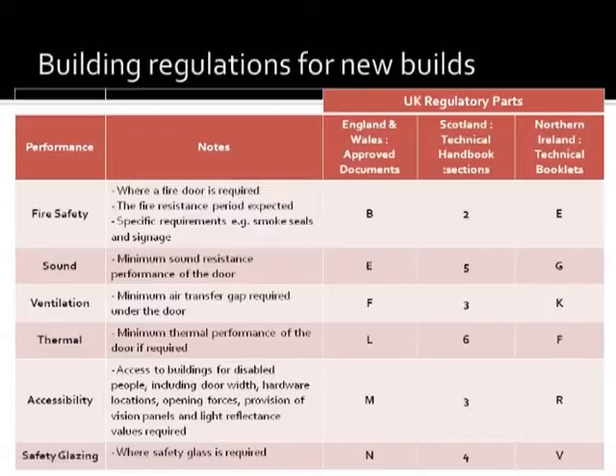Who's responsible for making sure these regulations are adhered to? Everybody in the chain is responsible — right from an architect or another specifier whose job it is to make sure that the doors are correctly shown on the drawings, right through to the installer who must make sure that the doors are installed correctly in accordance with those drawings. So if, for example, the door is specified as an FD30S, that means the architect must make sure there are correct smoke seals on those doors and the installer installs smoke seals to those requirements.